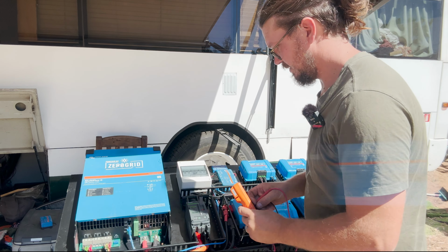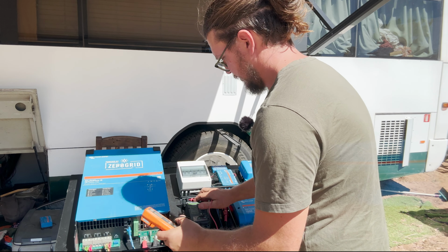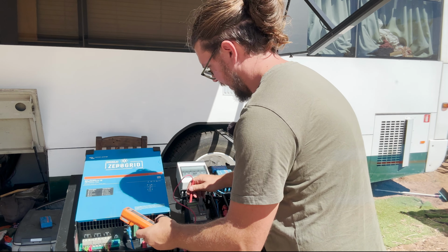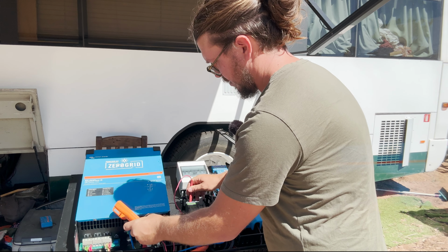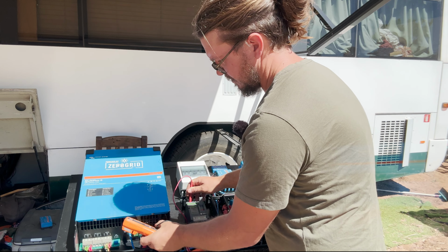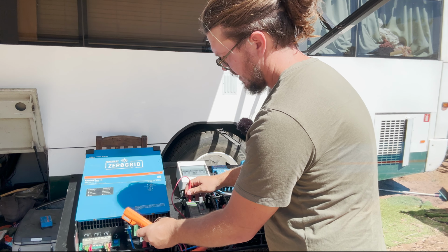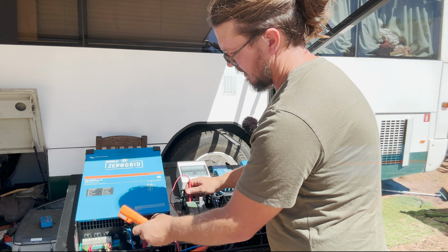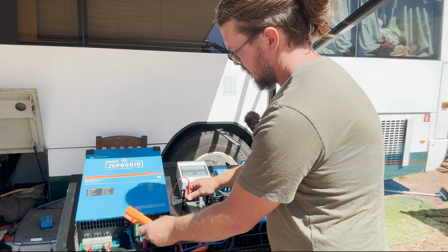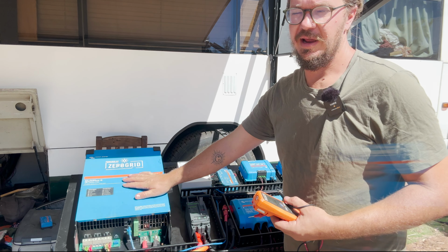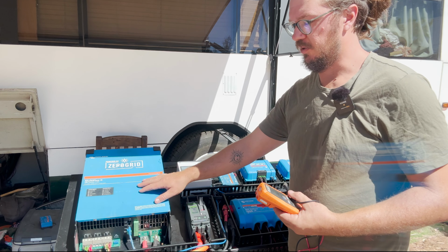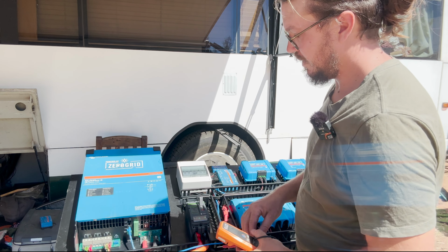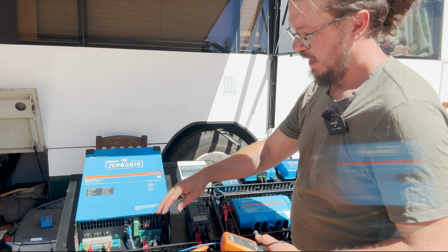So what we can do is simple things like have this on, just because I can't reach that terminal there, and we can test to make sure that it beeps as we'd expect, and we'd expect that not to beep. Actually, sometimes we do get a connection and resistance through the load itself, so if we were doing this test thoroughly, it'd be best to disconnect this cable and test it without it being connected to something.